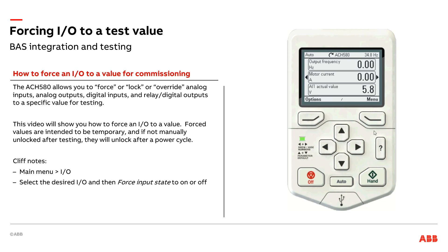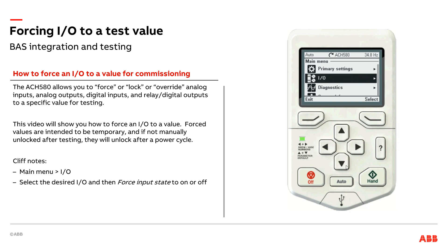On the screen on the right, I'm going to click on Menu, come down to IO, hit the right button, and now I'll be able to see the IO. I'm going to start with my digital inputs on top. As I scroll down, I'll see analog ins, analog outs, relay outputs — all my IO. When you see a zero here, that's the current value. So digital inputs 1, 2, 3, and 5 are all open right now, and digital input 4 is closed — that's my safety.